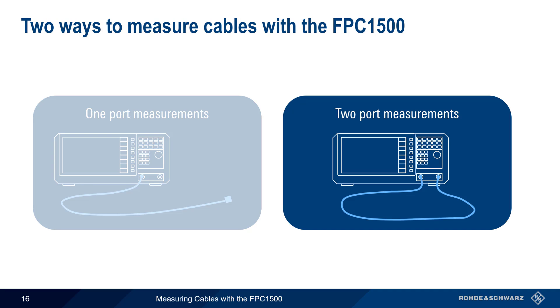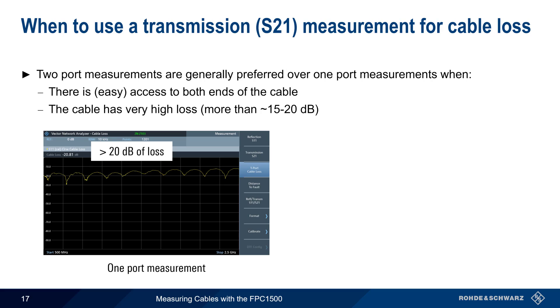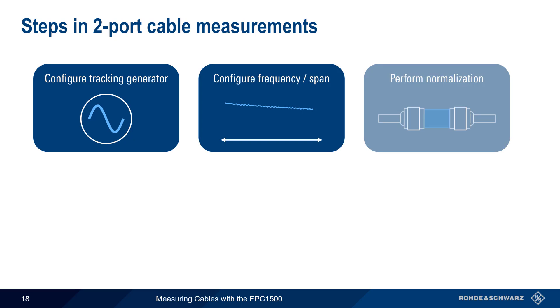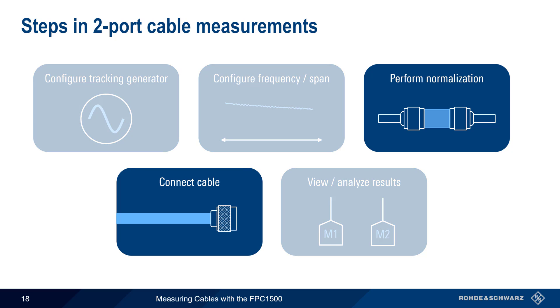Now that we've covered one-port cable measurements, let's look at how to make two-port cable measurements. Two-port measurements are generally preferred over one-port measurements in two cases: the first is when there's easy access to both ends of the cable, and the second is when the cable has very high loss, more than about 15 or 20 dB. High levels of loss tend to produce less accurate one-port measurements. For example, with more than 20 dB of loss, the one-port measurement results should be viewed with caution, and making a two-port measurement of the same cable provides a much more accurate and repeatable test result. The steps in making two-port or transmission cable measurements are: configuring the tracking generator, configuring the frequency and span, performing a normalization, connecting the cable, and viewing or analyzing the results. Most of these steps are the same as for one-port measurements, so we'll concentrate on the differences.